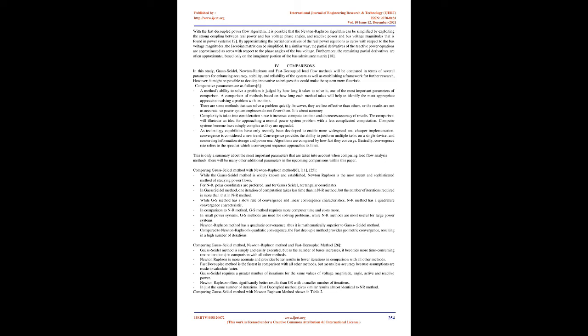However, there are several negative aspects of the fast decoupled method: more iterations are needed, even if the time for each iteration is less than with the NR method. Three factors essentially determine how accurate a fast decoupled load flow can be: the size and structure of the system, tolerances for convergence and the loading level of the system. Particularly in large and heavily loaded systems, even relatively small errors in state variables can result in larger errors in real and reactive power, though compared to line ratings, these errors are small. The accuracy of the solution can be improved by using a smaller convergence tolerance, which is a controllable parameter. FDLF and Newton-Raphson methods have proven effective and can be applied to larger and more complicated network structures, but FDLF enhances computational performance and can result in a cost reduction.